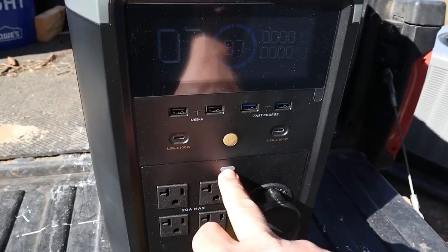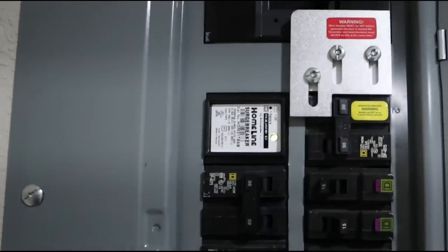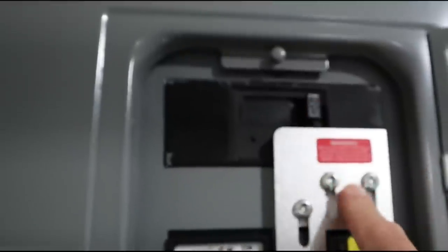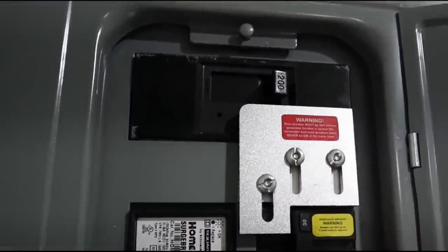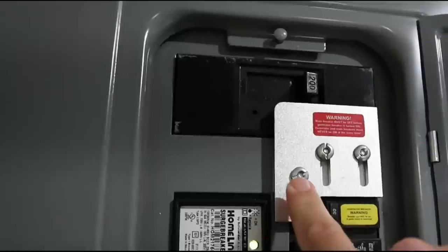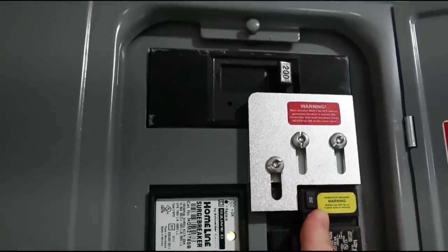The unit is powered on and lit up. 120 volts is going in, although we have to go flip the interlock inside the house. So let's come inside to our main panel. I have what's called a generator interlock kit — it's a very basic piece. We have main power coming in right now, and this is my generator plug hookup. It's two 120 volts in and we just jump it across both sides, technically bringing 120 volts to both sides of the panel. That's not a true 240 volts. What this generator interlock does is prevent me from turning on generator power to this panel while power is coming in from the power pole.